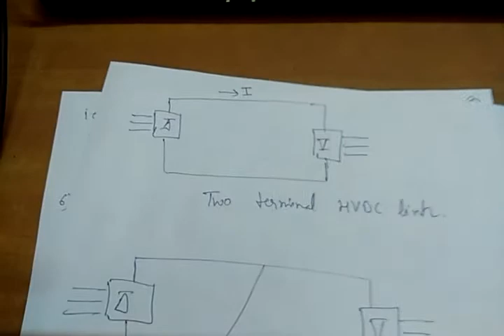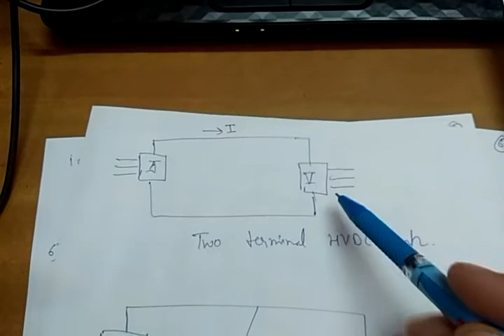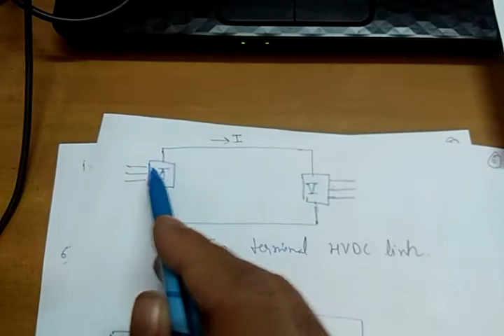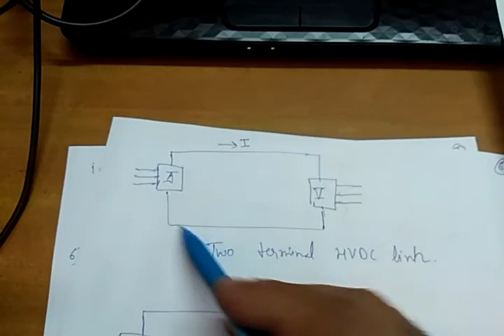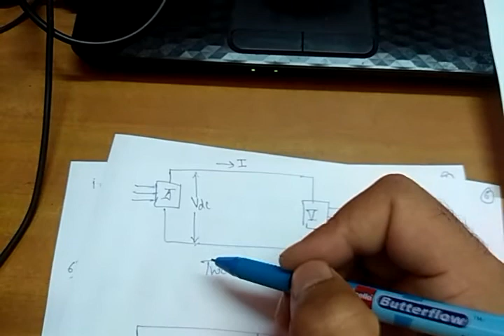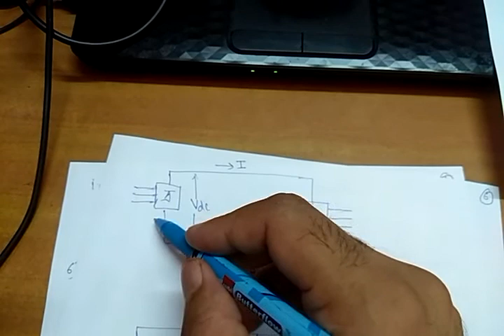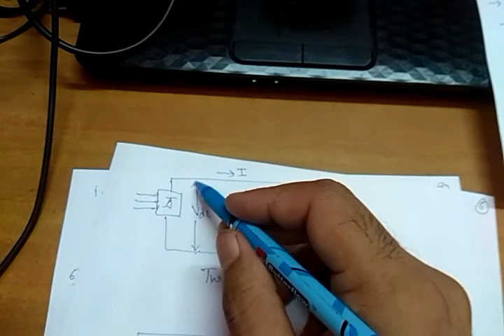This is the configuration of a two terminal HVDC station. Suppose this is our rectifier and this is our inverter station. These three lines I'm representing are the three phase system. This is the HVDC link and the current in this link is constant. What we are doing is varying this voltage VDC. We are controlling the power by changing the voltage. The current should be constant and the firing angles can be changed in such a manner that the power flow is controlled, which is done by changing the VDC.